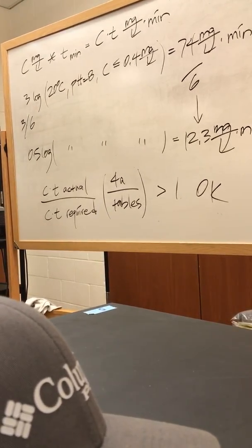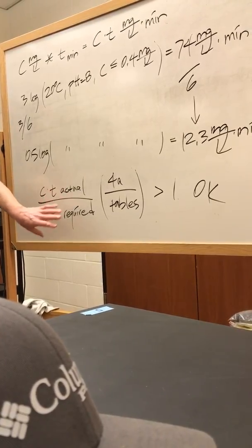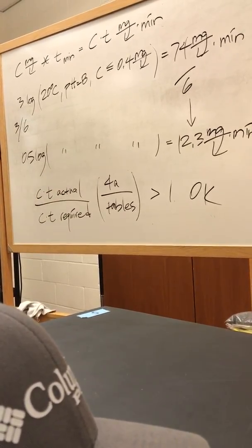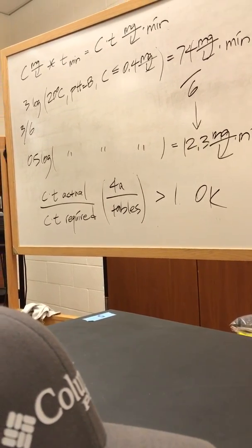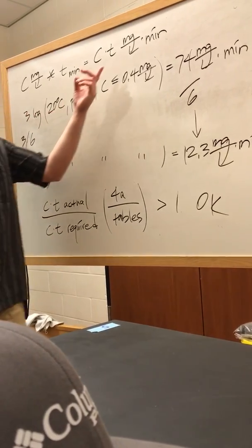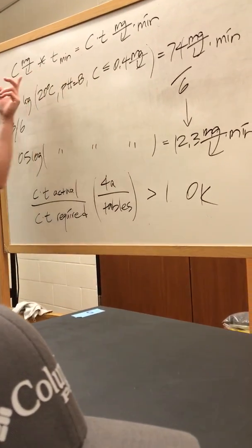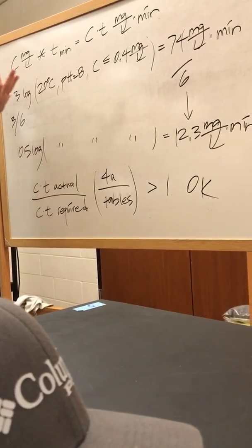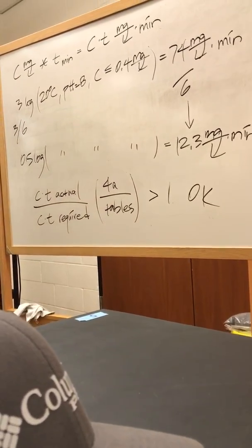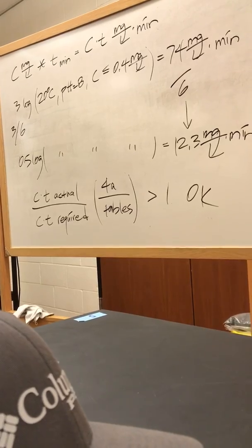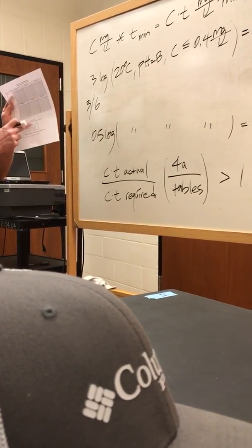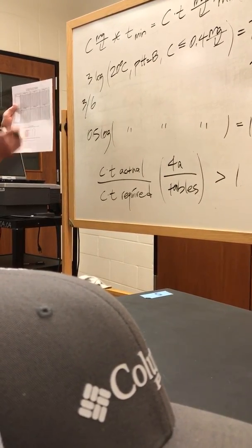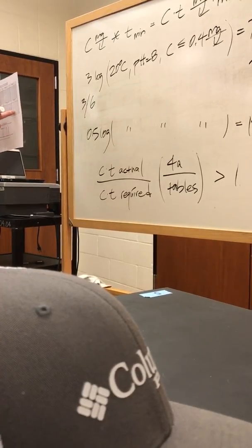So using the actual is pretty straightforward. I think in this problem, it just gives you a length of pipe, right? So you calculate detention time. And your concentration is going to be whatever you read with the meter. But to use these tables, for Giardia, this top table is Giardia, and this bottom table is for viruses. For Giardia, you need 3 log removal.